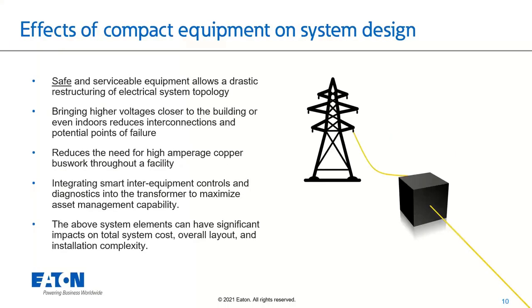So I kind of already drove this home on the last slide, but I've got my black box here. This is going to be representative of our AR-VFI transformer in a few slides here. But really, what does this do now that we say we did achieve it? We're smaller, we're safer, we're superior. What does that gain me in terms of my equipment? Is it worth it? What's the real draw for me as the customer, the owner, the contractor to do something like this? And what this really means is with these safer pieces of equipment, you can bring these higher voltage connections closer into the building or even all the way indoors. You can reduce the number of interconnections. You can essentially make a more smart integrated system that is less prone to failure, with fewer maintenance points and things like that.